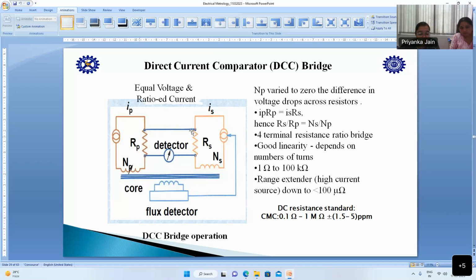So there is a difference in current, which is known by the detector. The difference in current will be adjusted here by the variable core again, and based on this adjustable variable core, the current on the standard as well as the DUT side will be the same, and the detector will deflect 0. That is I1 minus I2 equal to 0. Once the detector shows 0, the bridge is balanced. So IPRP is equal to ISRS. That is how the bridge is balanced here, based on this variable core, in the direct current comparator bridge.